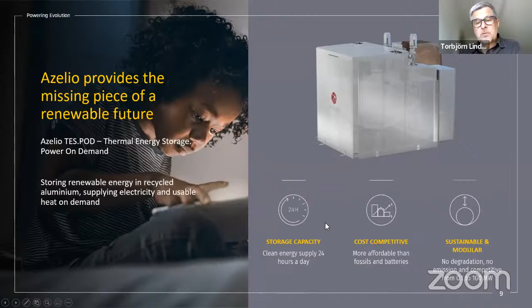In this example, the PV field we design supplies energy during the day to the customer. As a backup, when there are no renewables, we'd either need to be grid connected or have a backup diesel genset. The PV panels also charge the energy storage modules during the day, and at night during discharge mode, this storage is designed to cover most of the electricity needed by the customer. That's the 24-hour cycle: PV charging both the system and the storage during the day, then discharging at night.